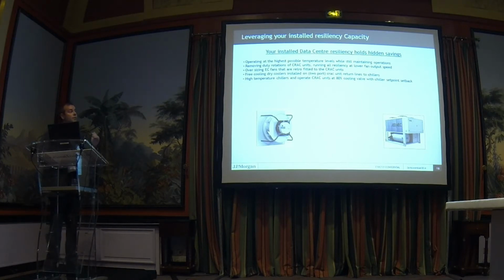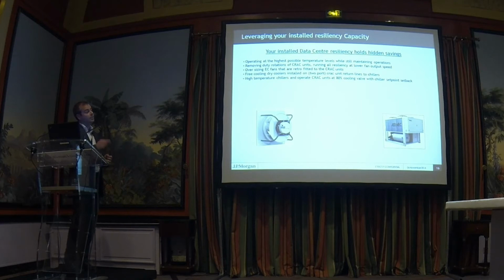Some of them will actually give you 30 degrees water out and 36 back. So if you'll run your data center at 26 degrees, 27, maybe even 30, you only have to supply water at 28. So in the middle of winter, the chiller's acting like a heater, if you like, because it's so cold. You get free cooling all year round. And the secret here is to run your CRAC units at almost 100%.